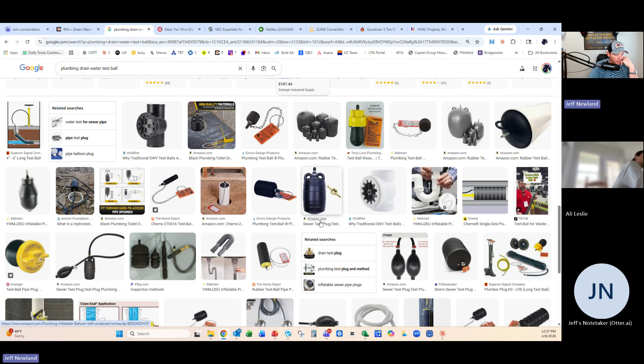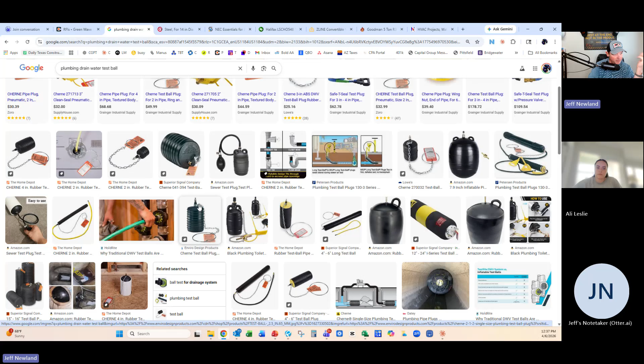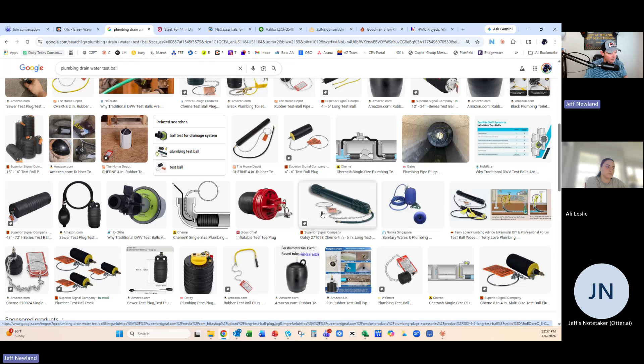So the important thing to remember is that it's not a... So you'll put test balls in all the other places it could potentially drain to, and that's what these are. Then you'd essentially have a standpipe full of water, and the inspector will want to see that still full of water when he comes back the next day, to make sure you don't have a leak somewhere. That's solely what that's for.